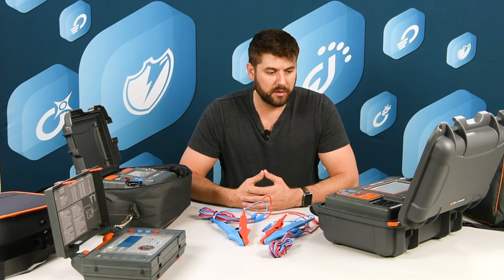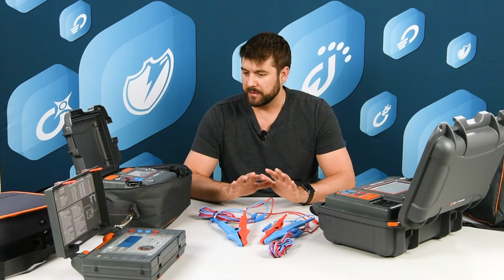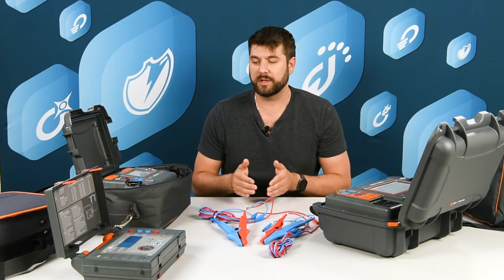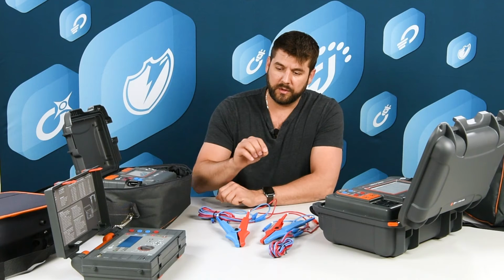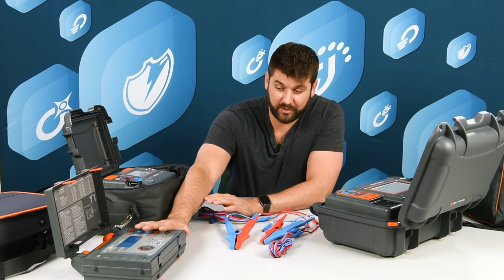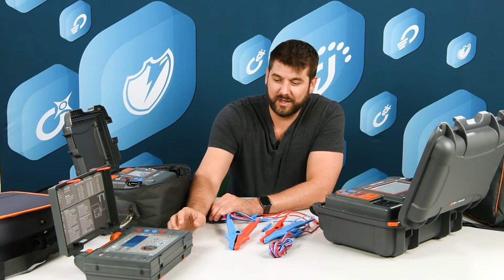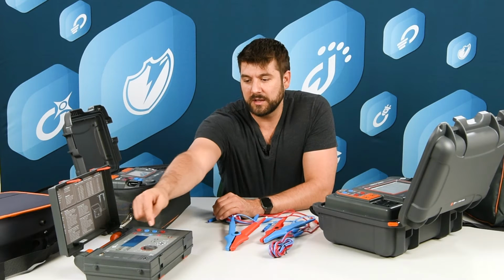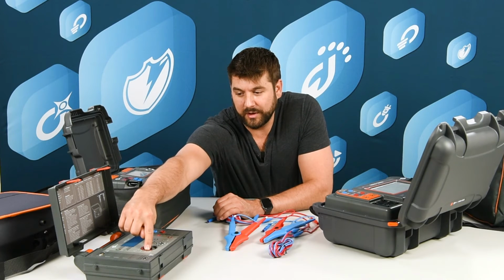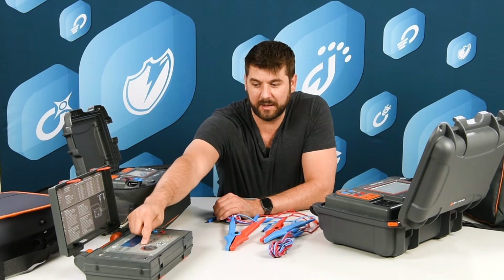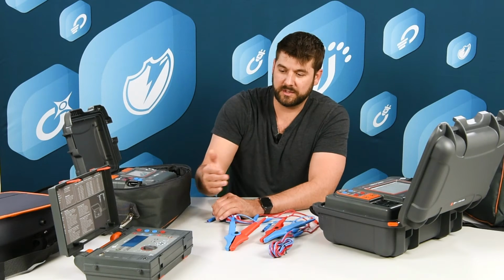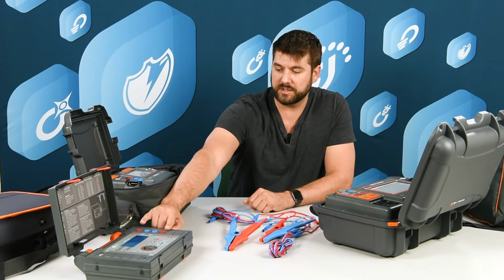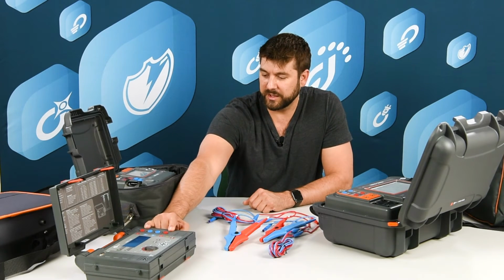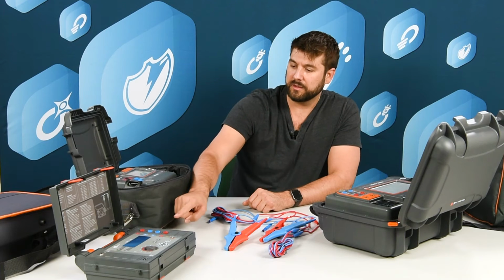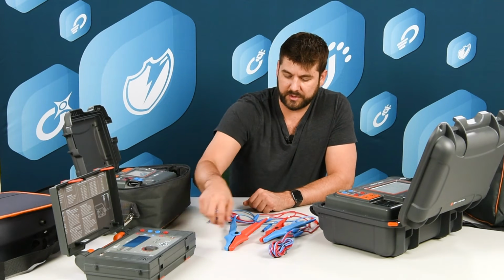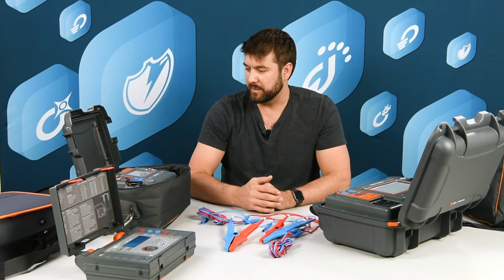So a microohmmeter is a device which pushes current and measures voltage. The old one we have here, the MMR620, is going to give us 10 amps, actually as low as 0.1 milliamps, all the way up to 10 amps test current. So you select your test current, 10 amps, and then it's measuring the voltage. You see our current channels pushing current through the device, and then we're measuring the voltage. So you just plug these in and make the measurement.